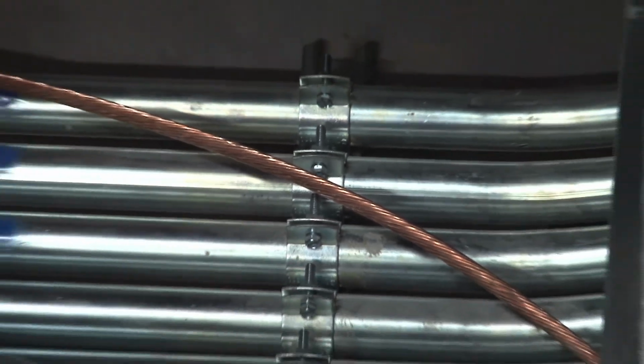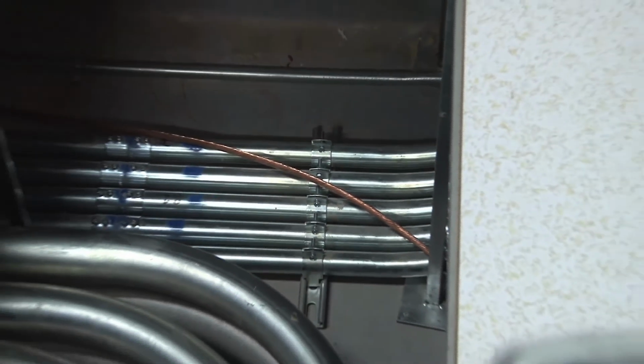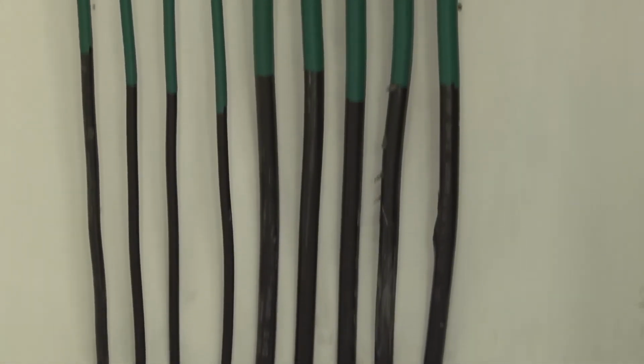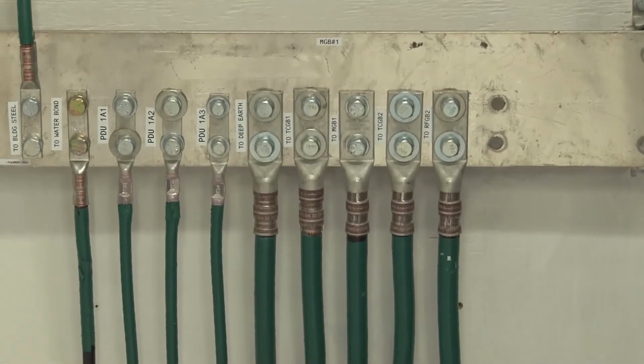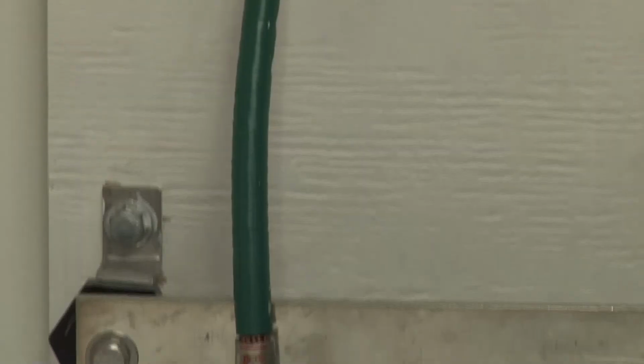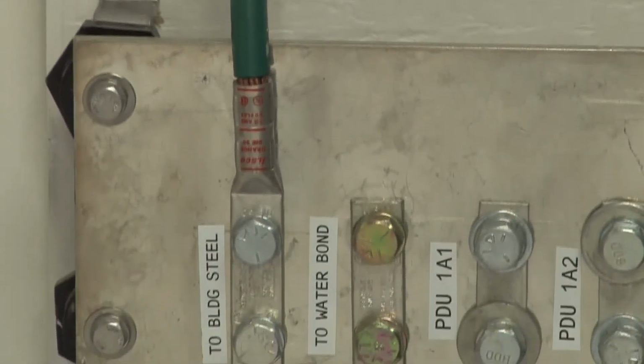We only use copper feeders, we only use copper lugs. CoSentry has a standard of copper connections only. We do not accept any aluminum connections. We do not allow this because aluminum is not a good conducting source. We do our annual retorquing, but with aluminum, I think I'd almost want to do a weekly retorquing. So we do not allow it. Everything in this building is copper only.